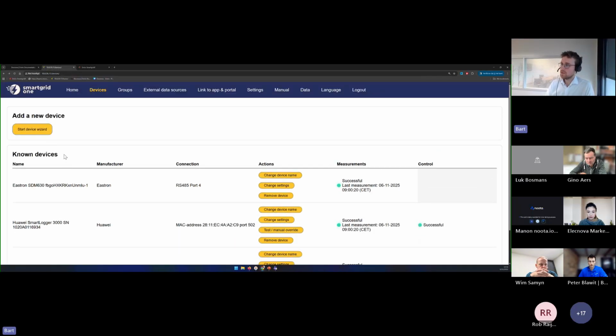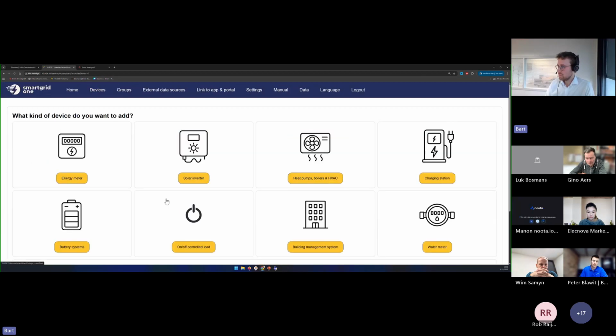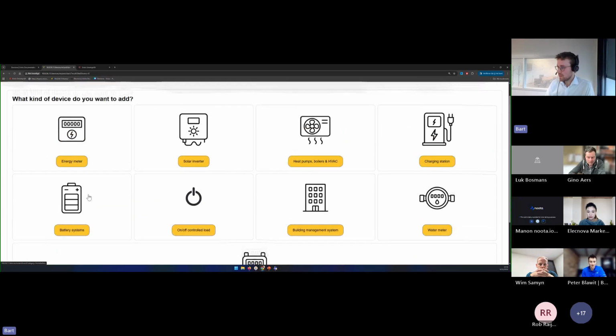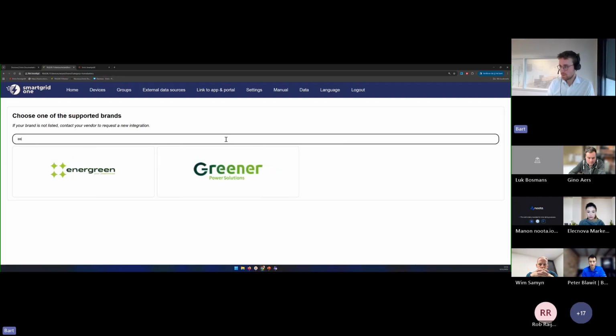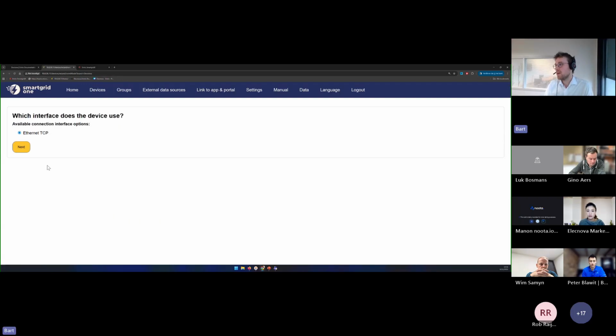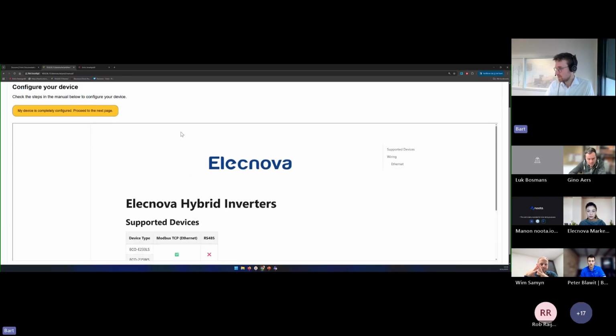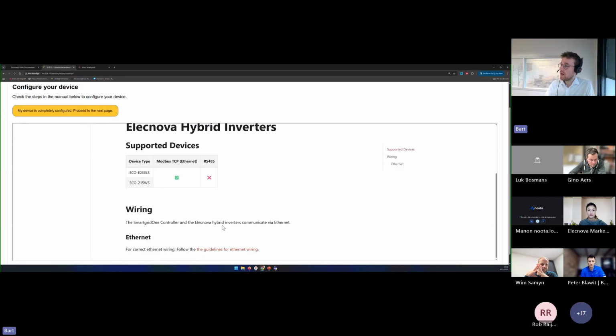With the device wizard on the energy management system, you can pick a battery system, which could be Elecnova. As you can see, we support the Modbus TCP interface for Elecnova, with these two types of devices supported. If not, you can go with the default option, 'my model or device is not listed.' If we pick this device, you can see some information about how to do the interfacing.